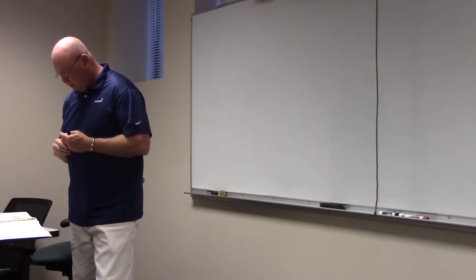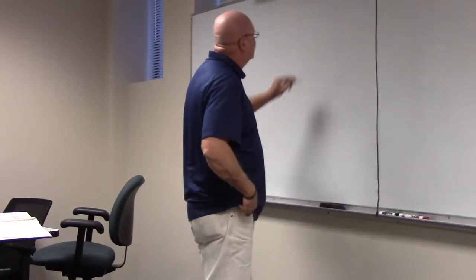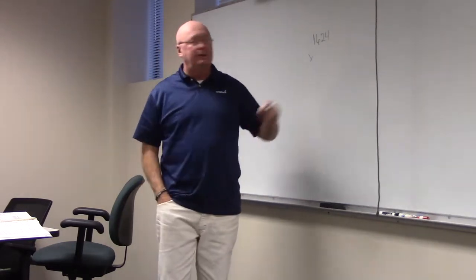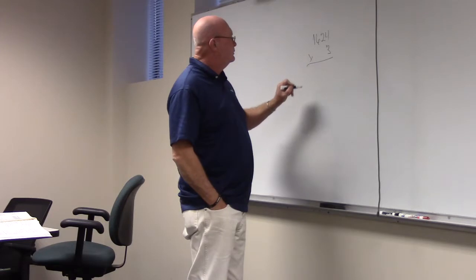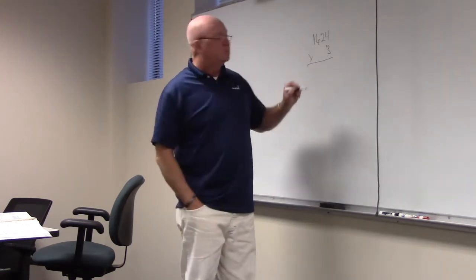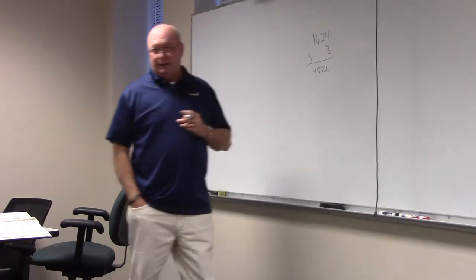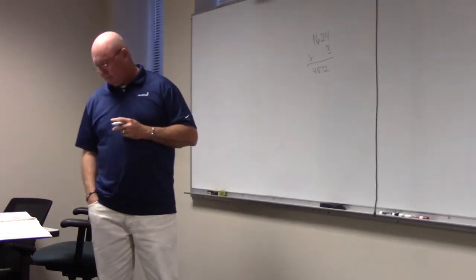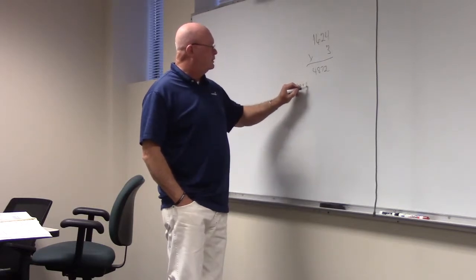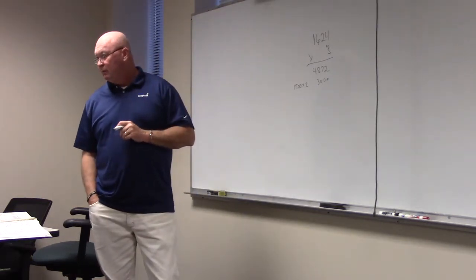It's a house. So first thing we're going to do is what? 1,624 times what? Three. And how much did that give us? 4,872. Okay. All right. Now we got what? How many small appliance circuits do we have? Two. And they're how much each? 1,500. Times two, so that's 3,000. You with me, Cameron? How did you figure out the two appliances?